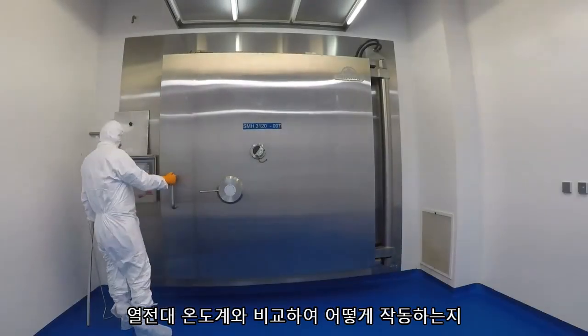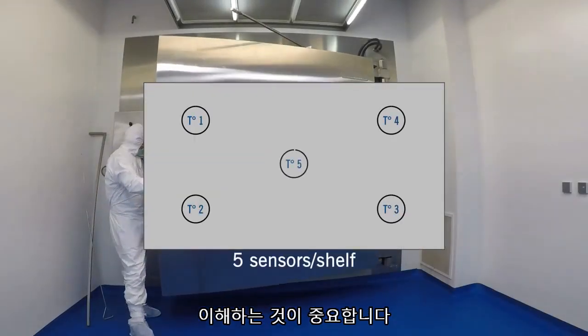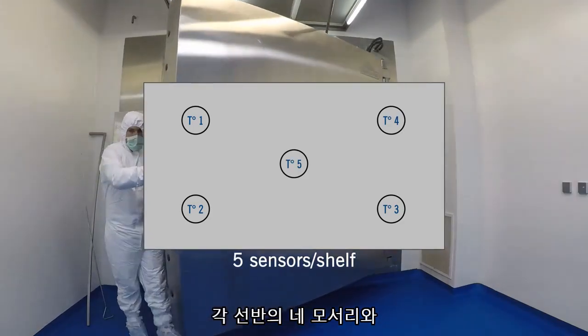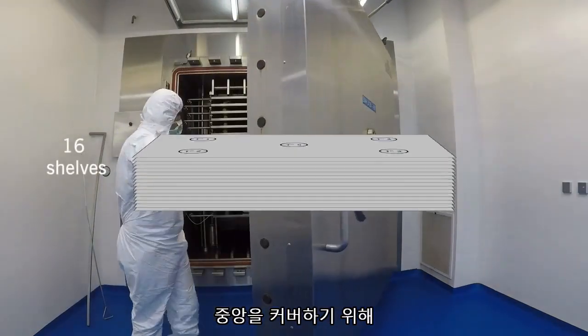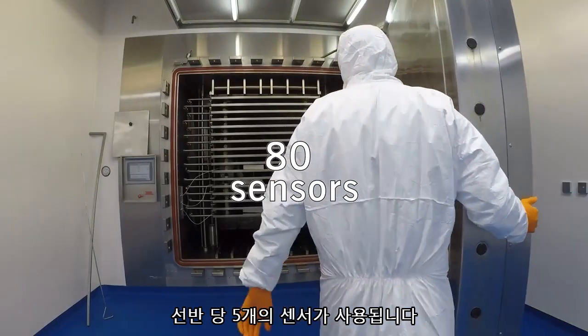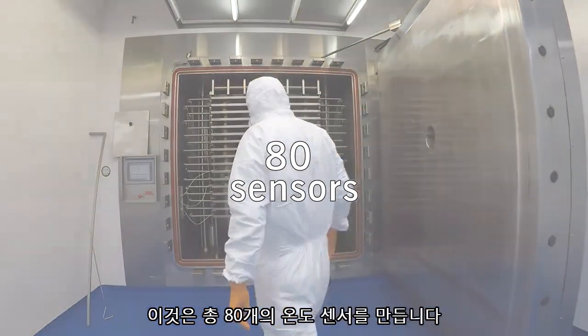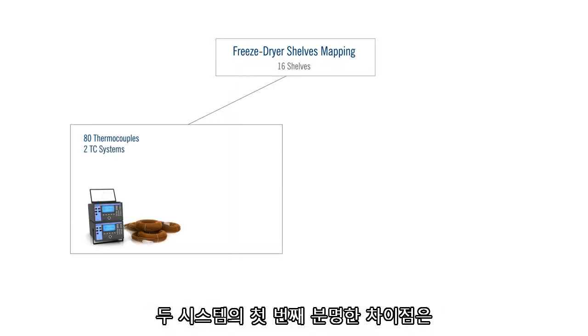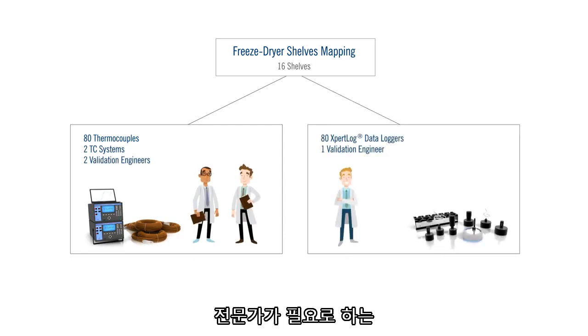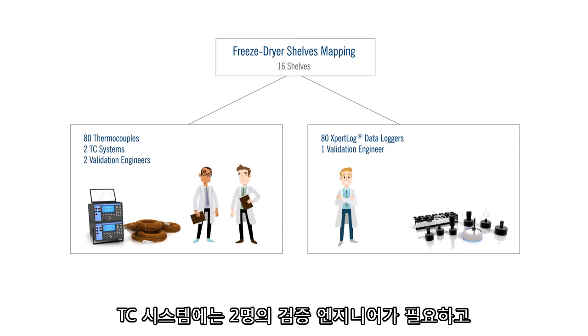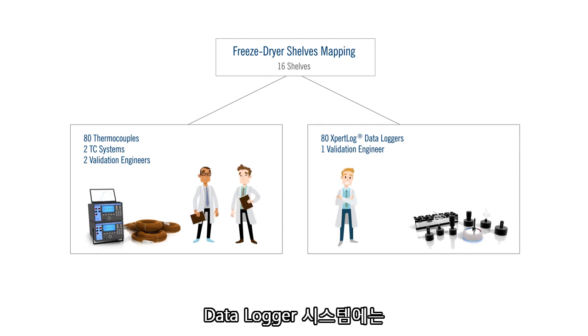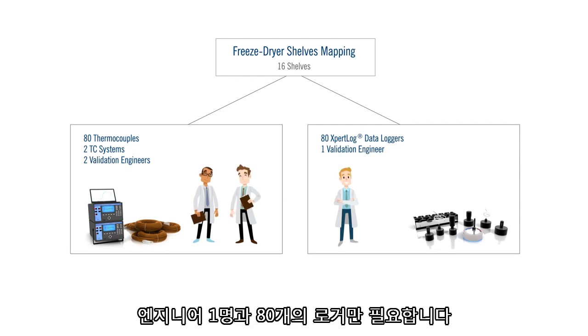compared to thermocouples. As per industry good practice, 5 sensors per shelf are being used to cover the 4 corners and the center of each shelf. That makes a total of 80 temperature sensors. The first obvious difference between the two systems is the hardware and manpower needed. While 2 Expert Val 60 TC systems and 2 validation engineers are needed for the TC system, only 1 engineer and 80 loggers are required for the data logger system.